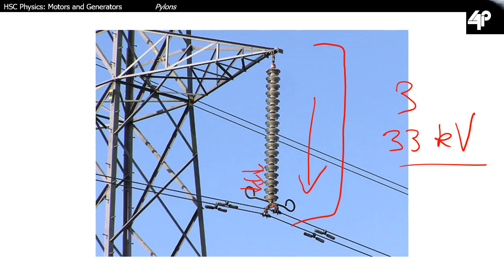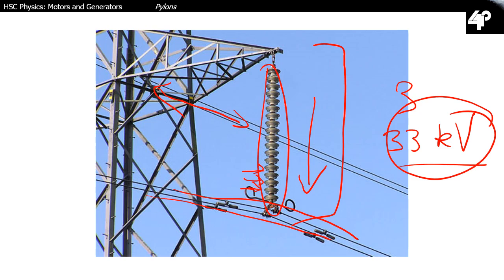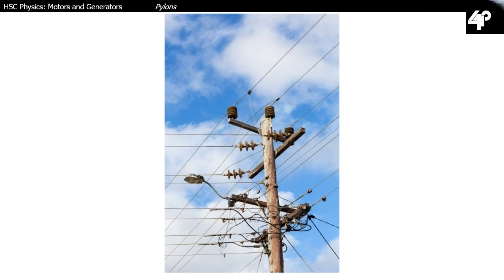But one thing that you can almost guarantee is that for any voltage through these lines that is above the 33 kilovolt mark, the power lines are actually suspended underneath the strain insulator here. And this is what's called a suspension insulator, because the insulator is dangling downwards and the power cable is attached to it at the bottom. And these are the ones that you're always going to see on the metal pylons. They're always going to be of the suspension design. So what about for voltages that are 33 kilovolts and below?